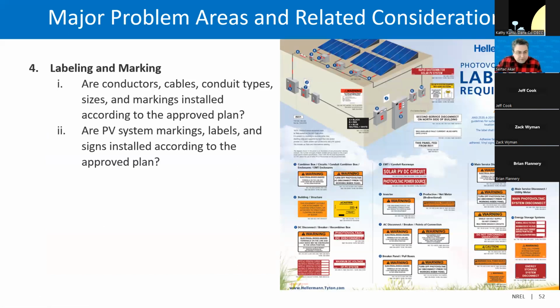Then comes the labeling. In the labeling, the inspector should verify that all the conductor cables, conduit types, and sizes are marked properly, and all the labels are placed according to the plan and in their proper location. Of course, we discussed that earlier in the chapter. They need to be weatherproof. If they are using adhesives, the labels should be visible, having proper fonts and sizes. These are actually easy-to-detect types of violations.